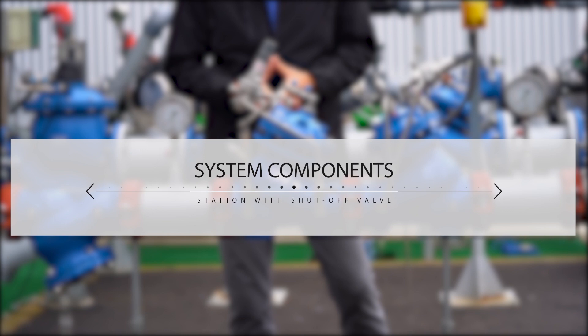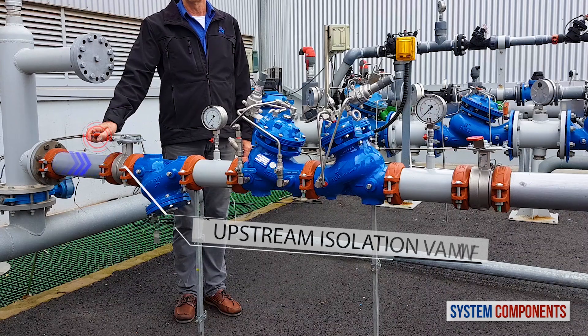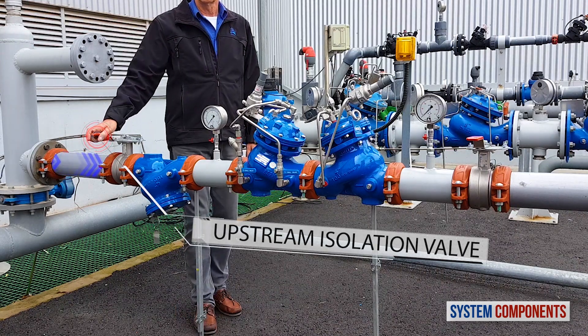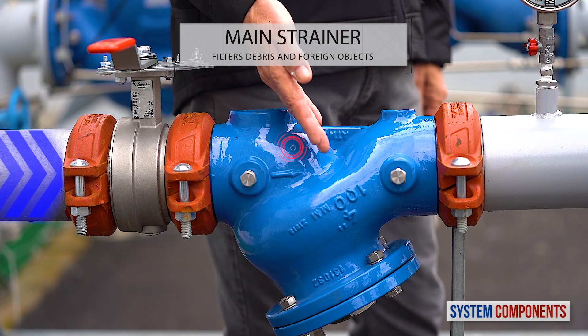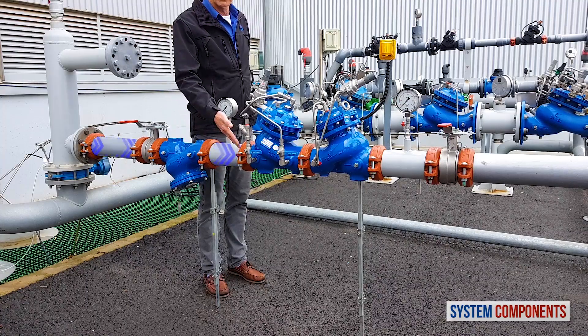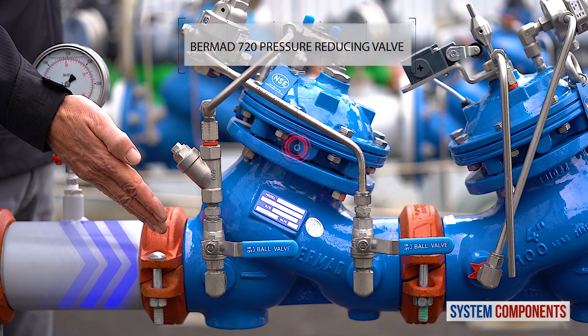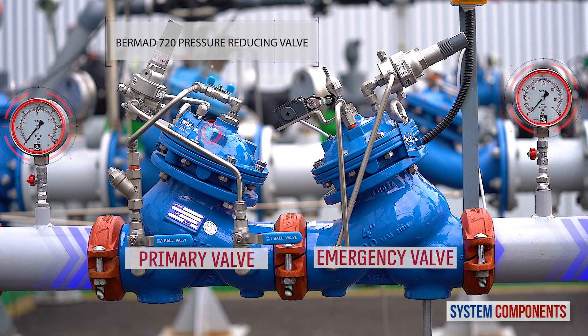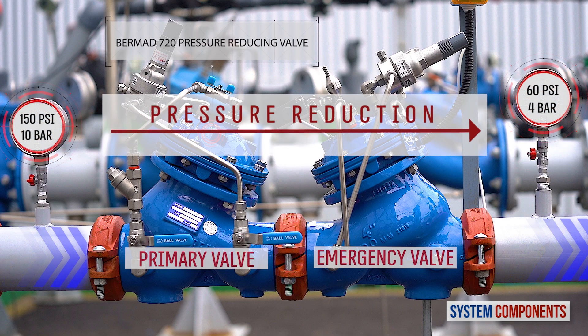Before we talk about commissioning procedures for this station, I'd like to present its major components. When the upstream isolation valve is open, water first encounters the main strainer, trapping any debris or foreign objects. The water then enters the primary Bermad 720 pilot-operated reducing valve. This valve is calibrated using a pilot to reduce the upstream pressure to the design pressure value for the consumer line.